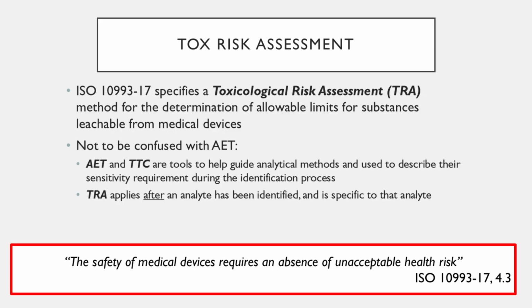So, what we're going to do is go through each and every analyte in order to understand what is the risk of that analyte and is that acceptable. Your medical device will only be deemed acceptable and shown to be reasonably safe if you can show an absence of any particular health risk with any analyte that you show.